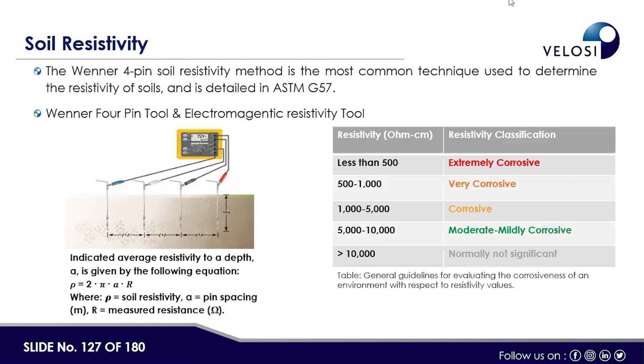For example, in the desert, sand is a very high resistivity environment and less corrosive, whereas near coastal areas it has very low resistivity and is highly conductive and highly corrosive. So resistivity and corrosivity are inversely proportional to each other. The higher the resistivity, like in sand dunes in the desert, the lower the corrosivity, meaning you need less current to fight corrosion.